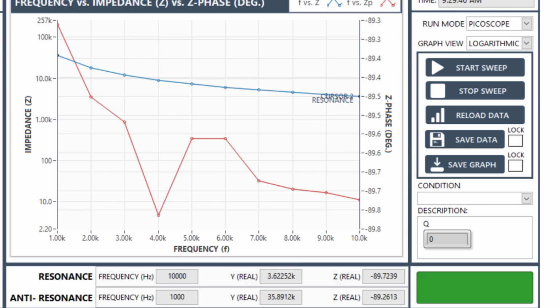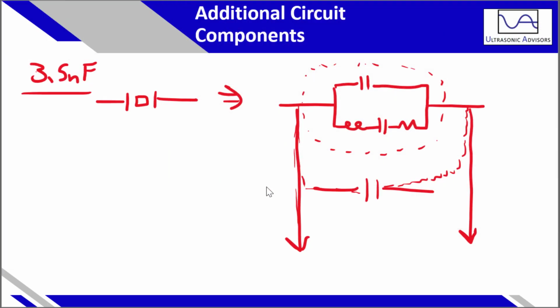It's 4.41 nanofarads. Alright, so the compensation was before set at 3.5 nanofarads. And because you're compensating so much, what's actually going to end up happening is that this capacitor will be almost eliminated completely from the equation. So there will be almost inductive properties, so that you actually subtract the effect of the capacitance.